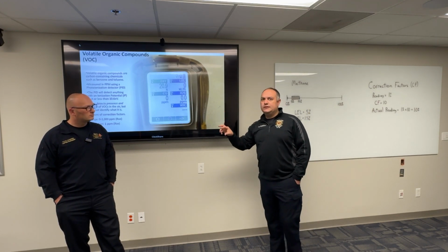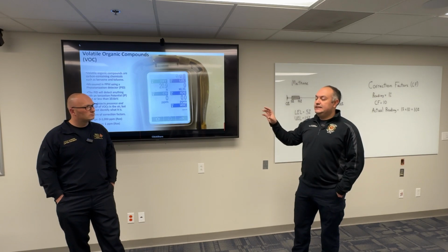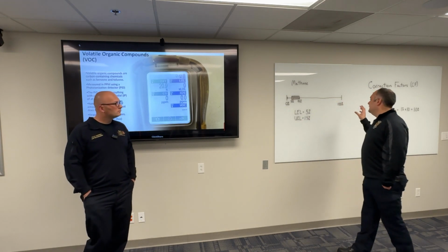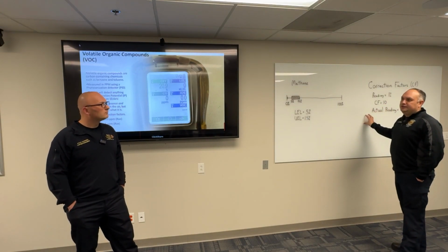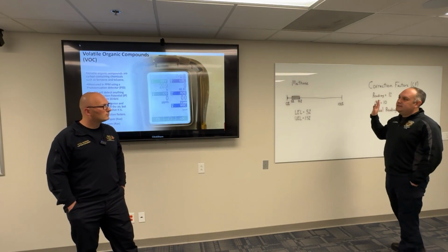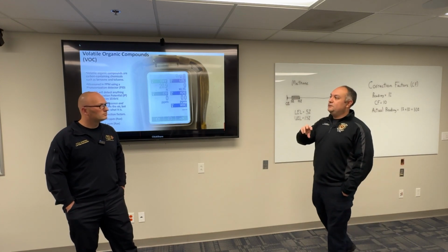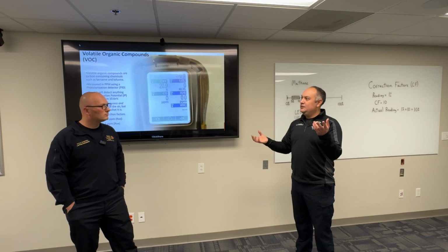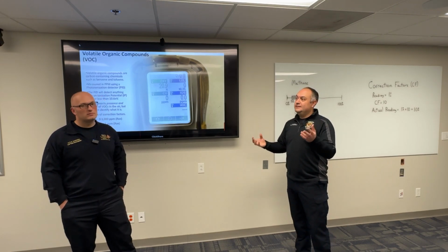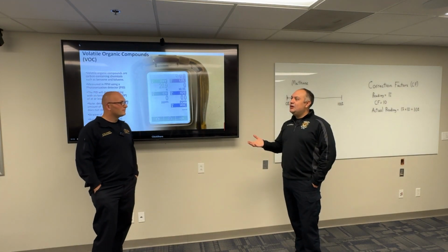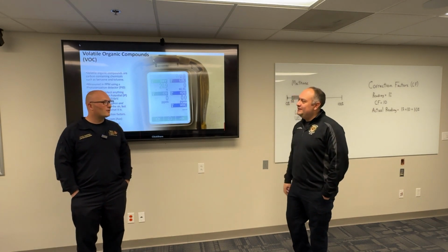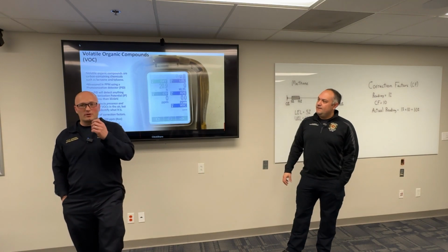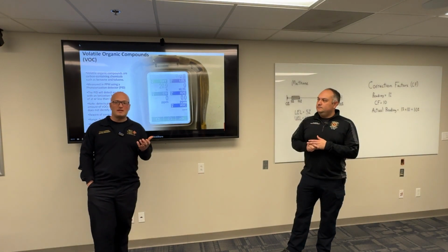Another thing that's really important, talking about the VOCs and the PID lamp, is, again, we talked about correction factors with the LEL. That is equally important with your VOCs because those range and vary depending on manufacturer. Even with RAE products, the bigger lamp and the smaller lamp have a lot different correction factors for the same chemical. So that's something you should probably know, and we all know that because we read our manual and know what our meter does. Exactly. That's another good point Nick brought up with finding this stuff in the NIOSH pocket guide.